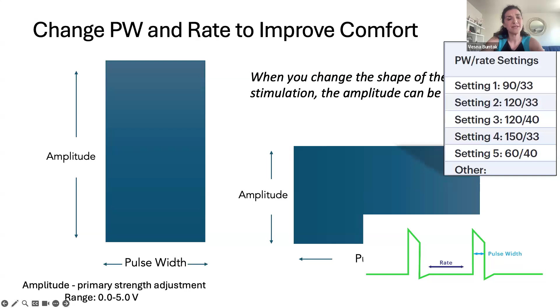If efficacy issues, defined as sleepiness or poor tongue movement, especially retraction or rightward deviation, are still present, changing electrode configuration can sometimes help. The whole system can be unipolar or bipolar. The cuff itself has 3 electrodes that can change polarity, and changing the electrode configuration of the stimulation cuff can capture different nerve fibers and significantly improve comfort and/or tongue motion. Note that when changing the polarity, voltage should be reduced by 50% when testing the new setting.